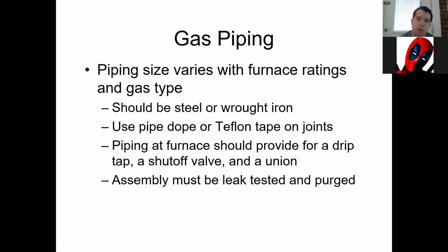So again, piping the furnace and fire drip tap, that's what I was talking about. Shut-off valve and some sort of connection. The shut-off valve is really important to have. It makes it so that you can operate the system safely, and it helps you as a technician for troubleshooting to cut down on your time.